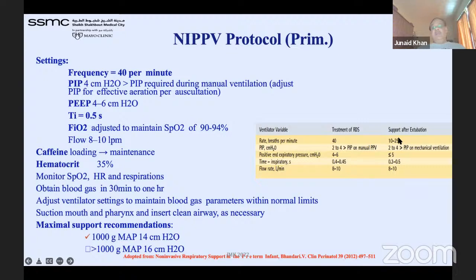It is published in NeoReviews. Whether you accept that or develop yours, this is the usual generalized guideline. So the rate, you will start with 40, a PIP of 2 to 4 more than the PIP on manual PPV, which is like 24, 25. Positive end pressure, as I said, 5 to 6, or 4 to 6 they said, but of course it is 5 to 6. The inspiratory time is 0.4 to 0.45, maximum 0.5, and the flow rate has to be 8 to 10 liters per minute.